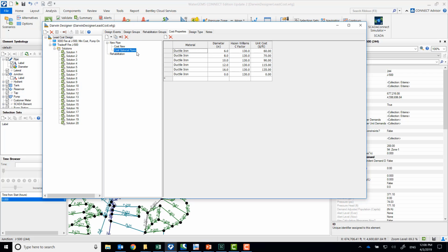And the optional pipes is the cost that we'll be assigning to the 600, 700, and 800 routes, which notice includes a 0-inch diameter, which makes it be optional, right? So we're not telling it to size all the 600 routes, all the 700, and all the 800. Most likely what we're going to see in our results is that it chooses one of those paths, or maybe if it really feels that we're doing a trade-off and we want to improve the pressure by quite a lot, it will do 2 runs, right? Obviously at a greater cost. But that's what this 0 diameter means.